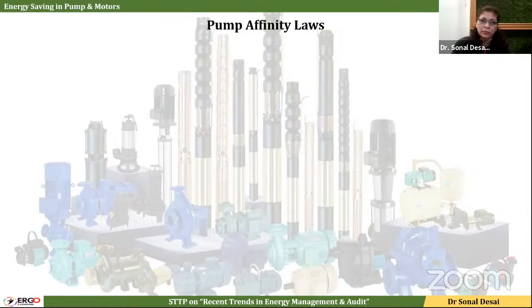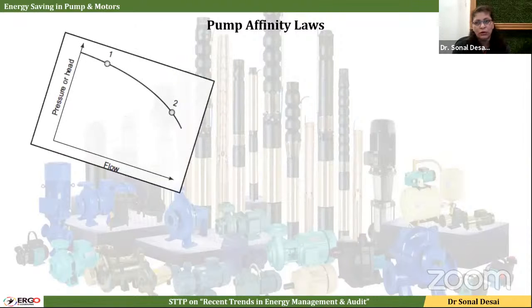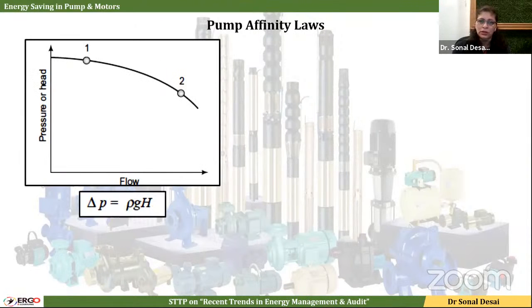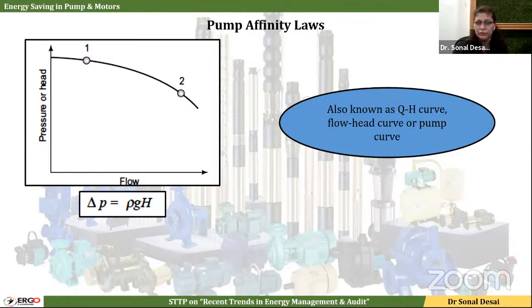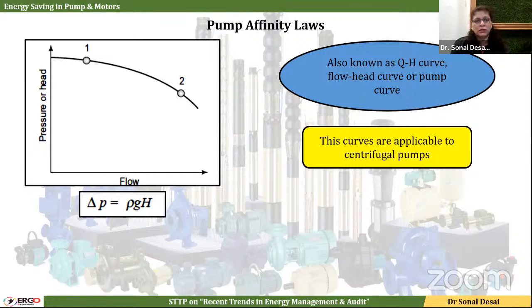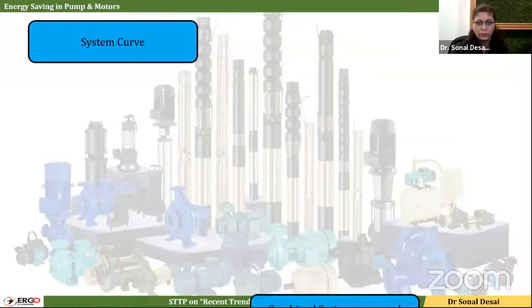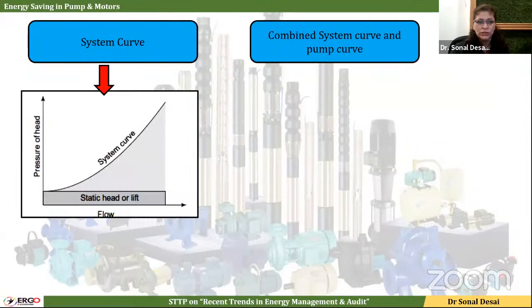When we talk of a pump, a very important aspect is the pump affinity laws, because they ultimately decide the governing of the pump. When we draw the diagram of pressure versus flow or head versus flow, it is called the pump affinity law. How they are important, we will see in the subsequent slides. These head versus flow curves are also called QH curves or pump curves, and right now they are shown for centrifugal pumps only. The system curve, which again is followed by a pump, is pressure versus flow, shown here.